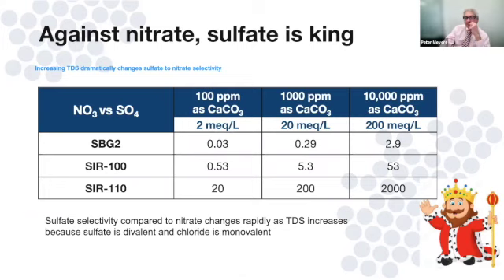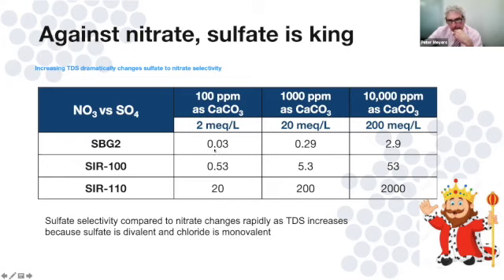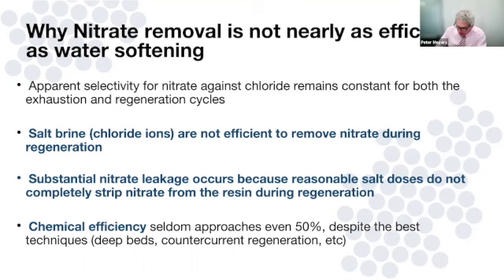Putting it all together for nitrate against sulfate: because these are binary equations with chloride as the reference ion, we calculate the nitrate-to-chloride and sulfate-to-chloride relationships, then ratio the two. SBG2 does not like nitrate relative to sulfate; SIR-110 loves nitrate. Overall, nitrate removal is not nearly as effective as softening — you get substantial nitrate leakage and don't get anywhere near the same chemical efficiency.